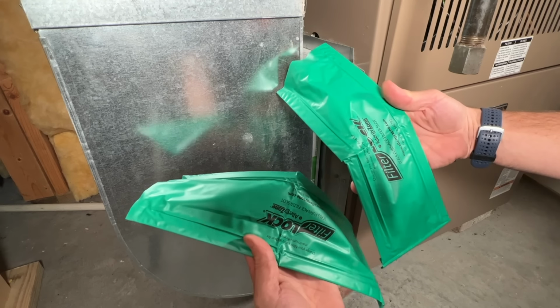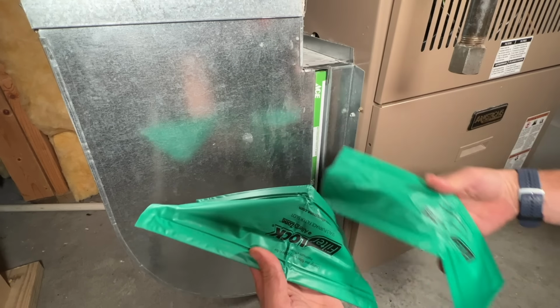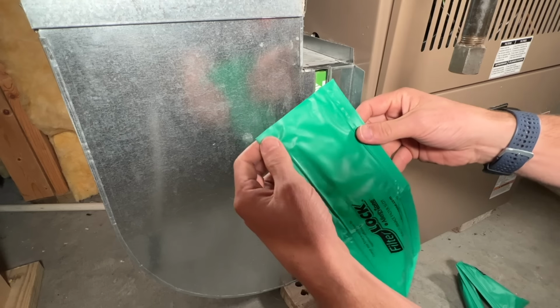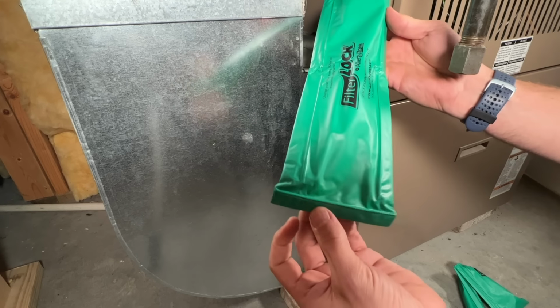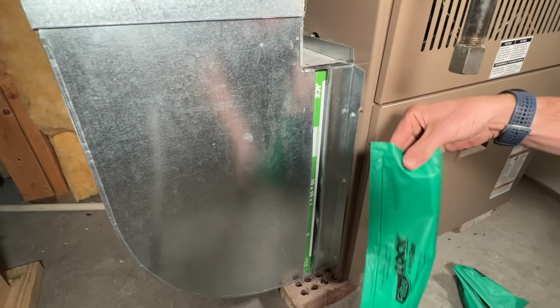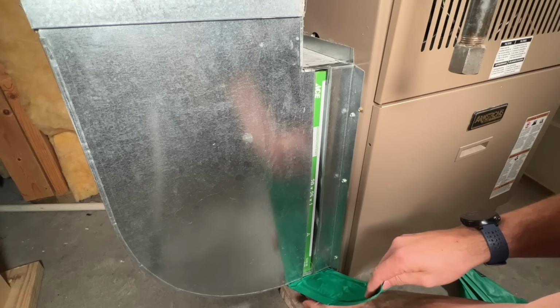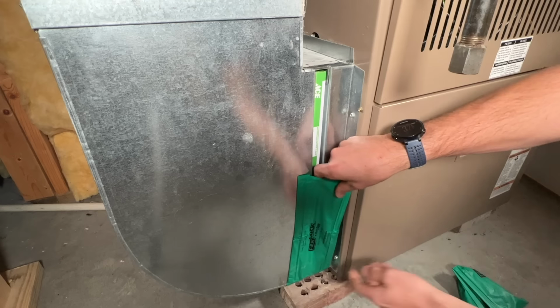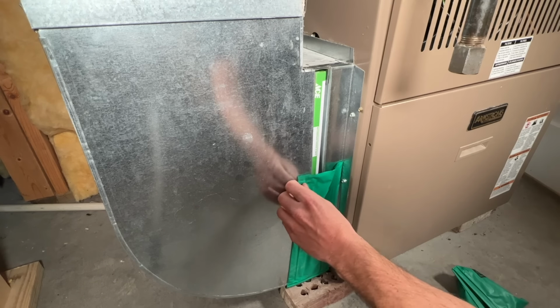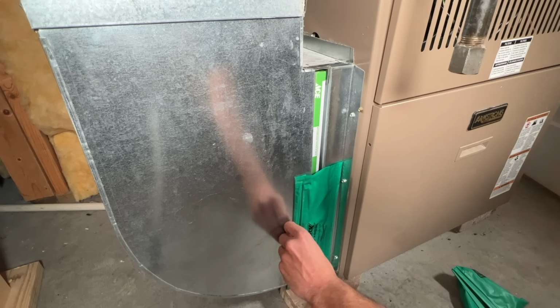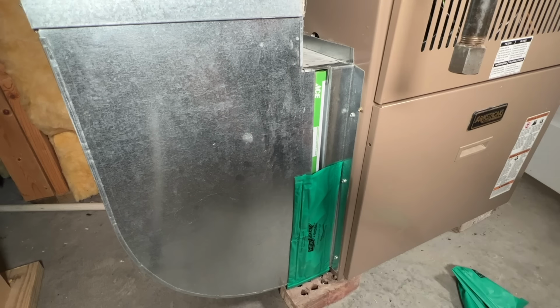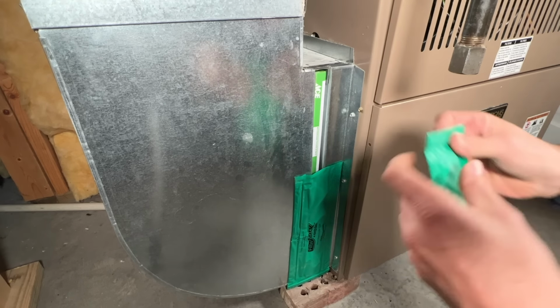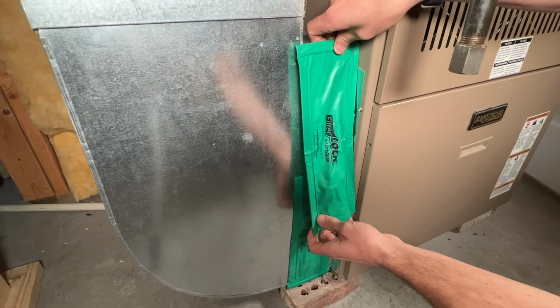I'll install it right here, and then we'll do that same test again to see if that smoke gets pulled into the ductwork. So the filter seal will come with two different halves, and that's actually what makes it so flexible. And then you'll have magnetic strips on the side and each of the tops and bottoms. So first up, we'll put the bottom on. So I'll put the magnet strip on the bottom of the ductwork, and then attach the side strips, adjusting slightly so they fit the overall installation that I'm dealing with. And then we'll go ahead and do that same thing for the top one.